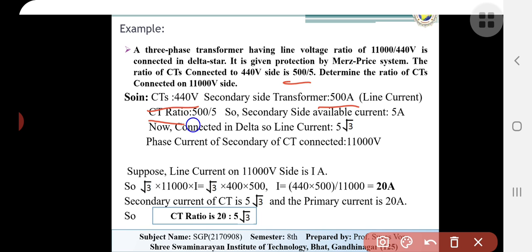So the CT ratio is 500/5. The secondary side of the CT is 5 amperes. Now this one is connected in delta, so the line current is 5√3. So the phase current of the CT is, we have to find on the primary side, the 11,000 side. Now the line current is 11,000 side.